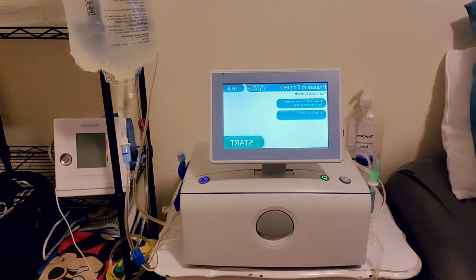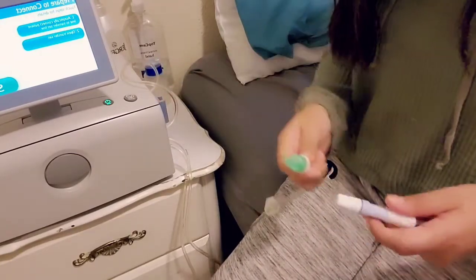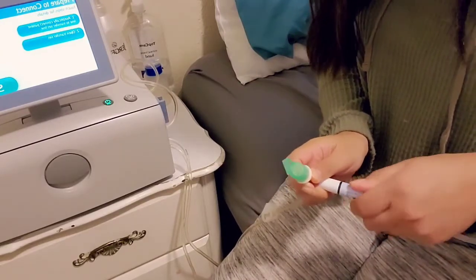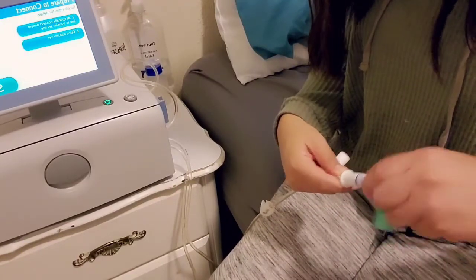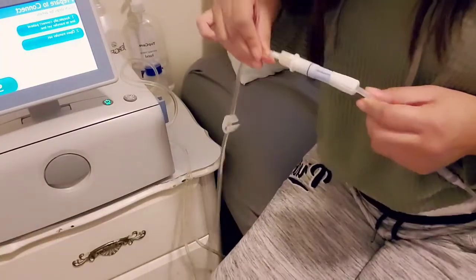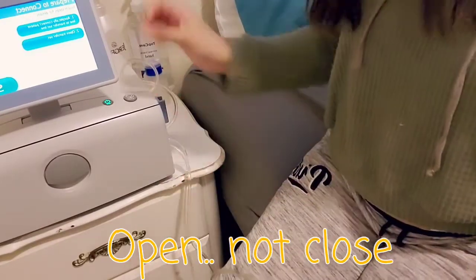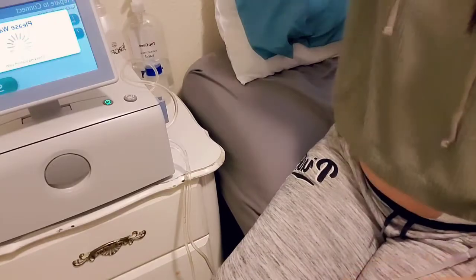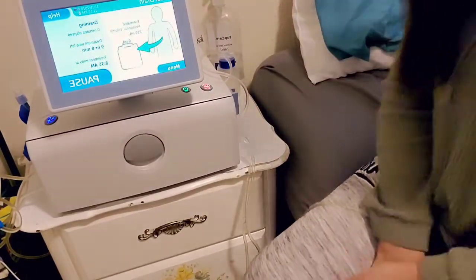Now that the cassette, heater bag, and patient line have been primed, press next. It tells you to connect yourself. Make sure your hands are washed and you've applied hand sanitizer. Here's my catheter — I grab the patient line, uncap myself first, and then do the prime line connection. It's connected. Make sure the line is unclamped and you can move freely. Close the machine and press start. This is what the machine looks like when it's draining. It'll dim so you can sleep. See you in the morning.